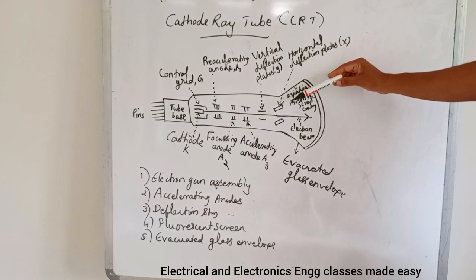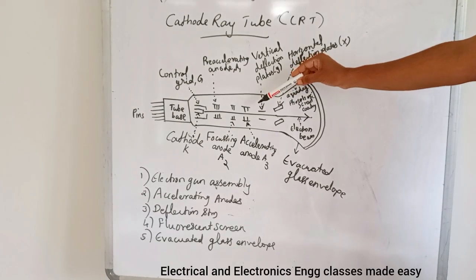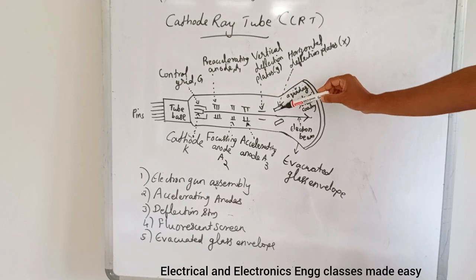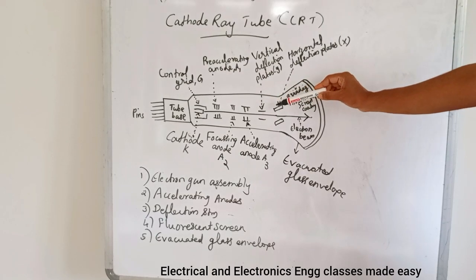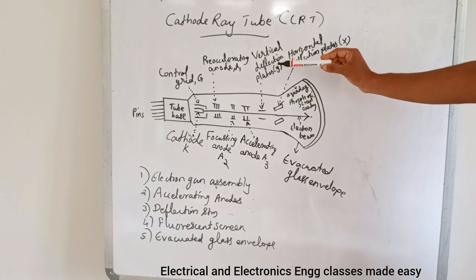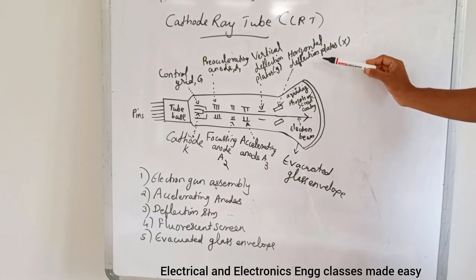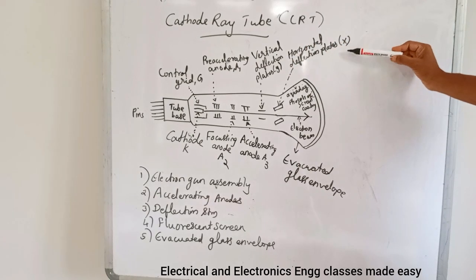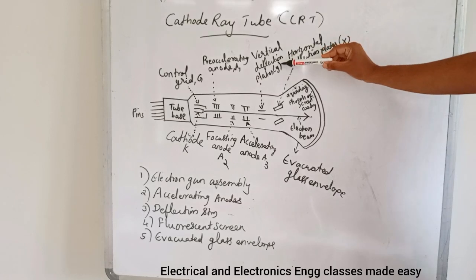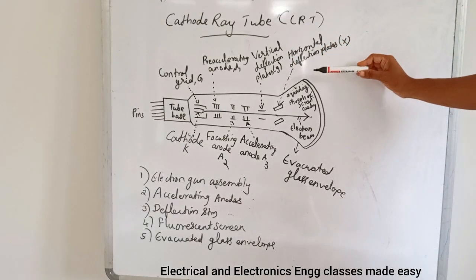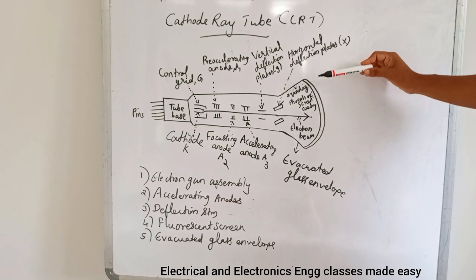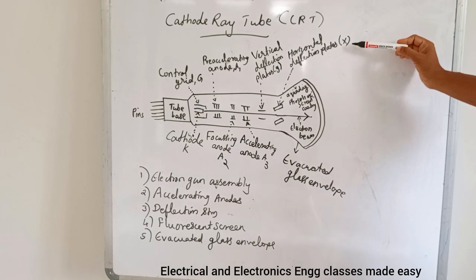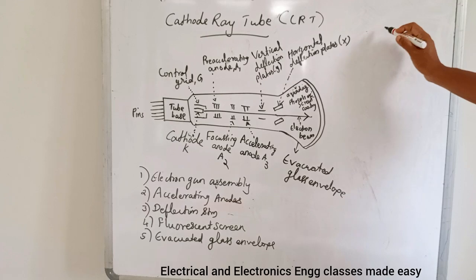After the electrons leave the electron gun assembly, they pass through a region controlled by the deflection plates. The deflection system consists of a pair of horizontal deflection plates and vertical deflection plates. The horizontal deflection plates are called X plates and the vertical deflection plates are called Y plates. A positive voltage applied to the X plate will deflect the beam towards the right, that is the positive X axis.